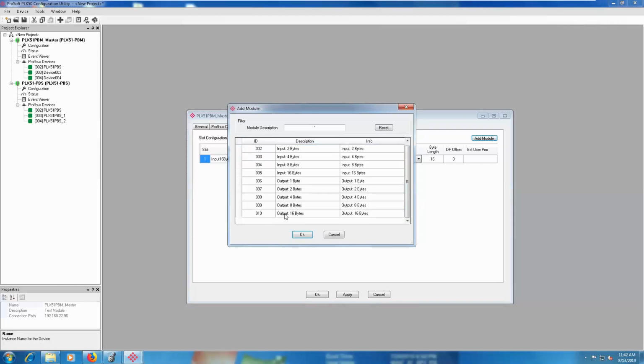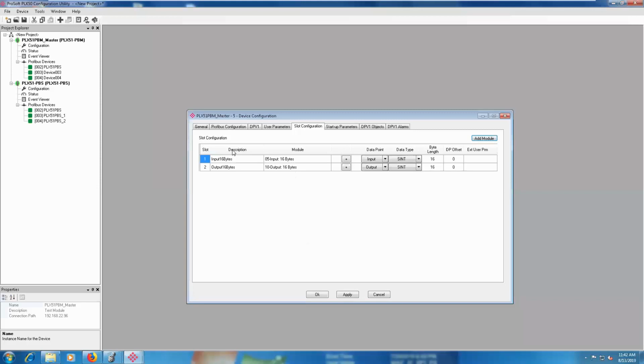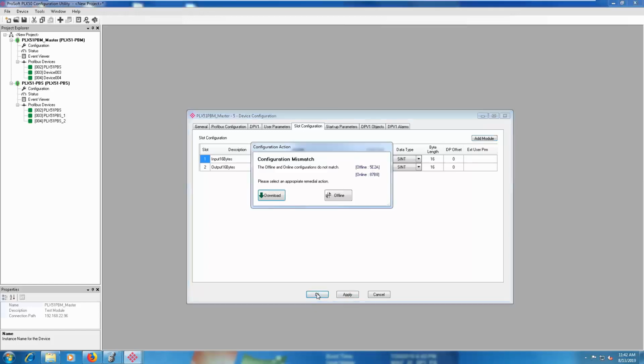On various devices, this is all based on the GSD file, so something like a drive may have all this information mapped in as far as your start bit, jog, shuttle, as well as your speed index or reference parameters. That's all based in the GSD file itself. And so you could add that device into the network. And at that point, you could download this configuration directly to the module. You can also store that offline.